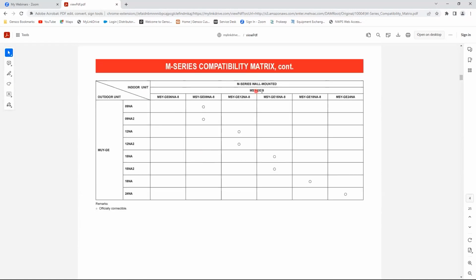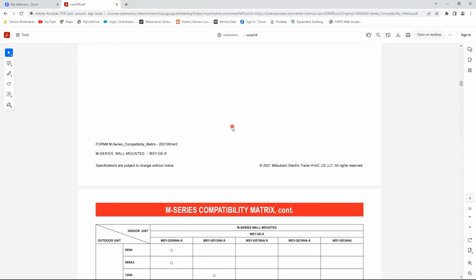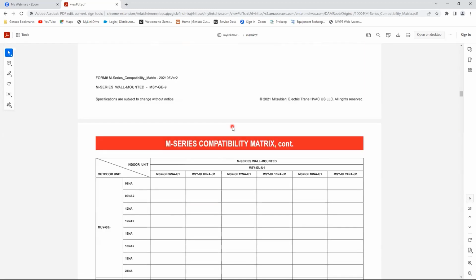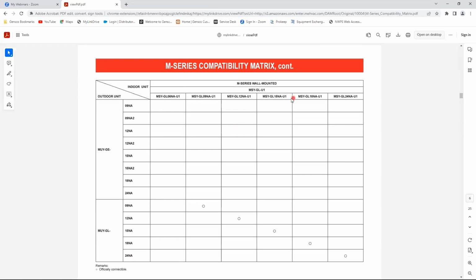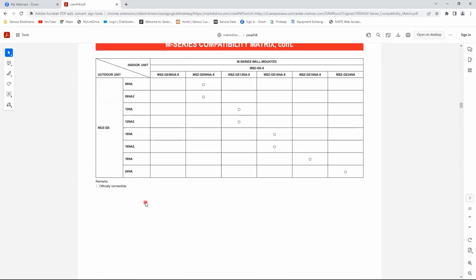So we have an MSY cooling only GE8, which gives you the size—06, 09, 12—these are your indoor units up top, and on the left-hand side, your outdoor units. If there's a circle in that box, that's a match. Be careful on these, because it gets a little tricky—even though the size might match up, if it's a -U1 or -U2, it may only be compatible with a certain outdoor unit, so pay attention and be careful to select the correct one.